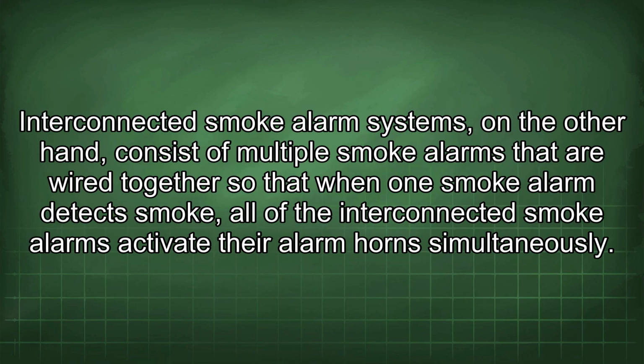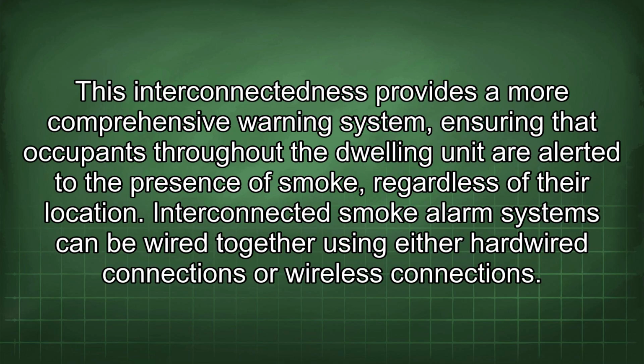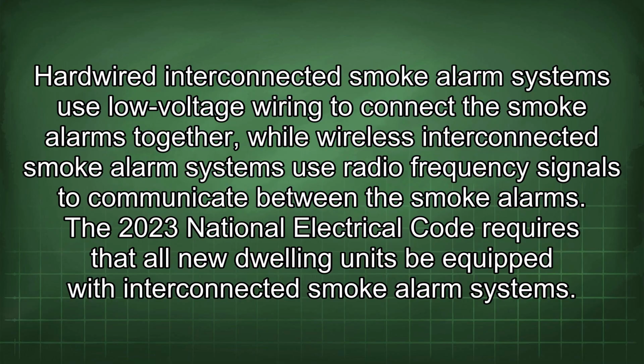immediate vicinity. Interconnected smoke alarm systems, on the other hand, consist of multiple smoke alarms that are wired together so that when one smoke alarm detects smoke, all of the interconnected smoke alarms activate their alarm horns simultaneously. This interconnectedness provides a more comprehensive warning system, ensuring that occupants throughout the dwelling unit are alerted to the presence of smoke, regardless of their location. Interconnected smoke alarm systems can be wired together using either hardwired connections or wireless connections. Hardwired interconnected smoke alarm systems use low-voltage wiring to connect the smoke alarms together, while wireless interconnected smoke alarm systems use radio frequency signals to communicate between the smoke alarms.